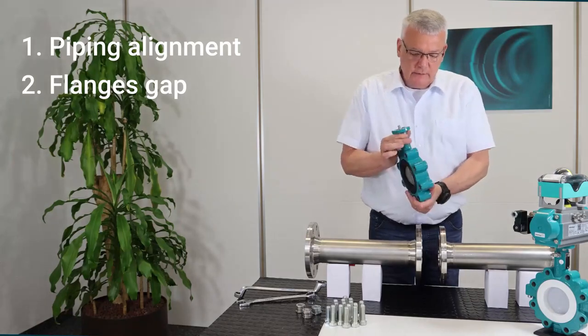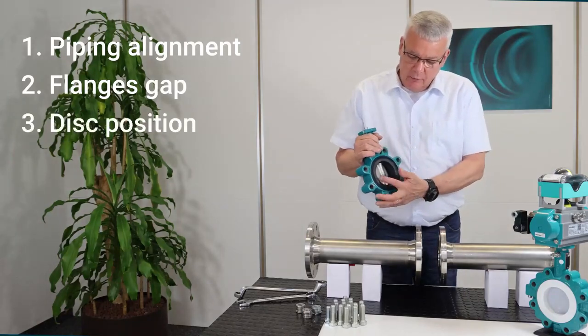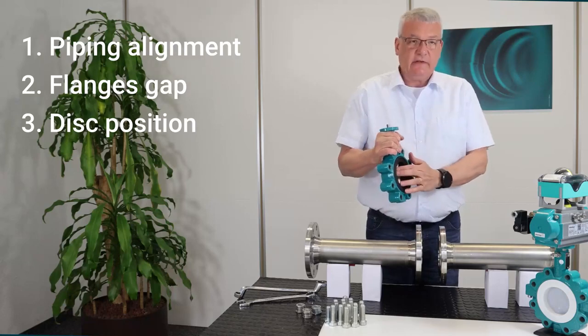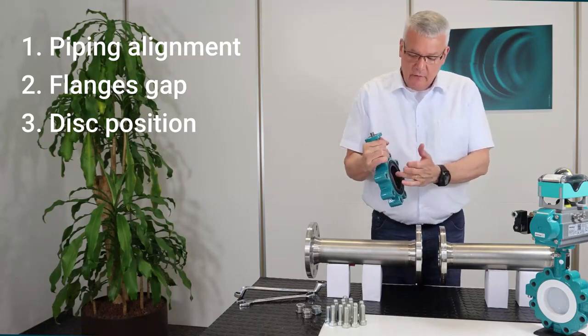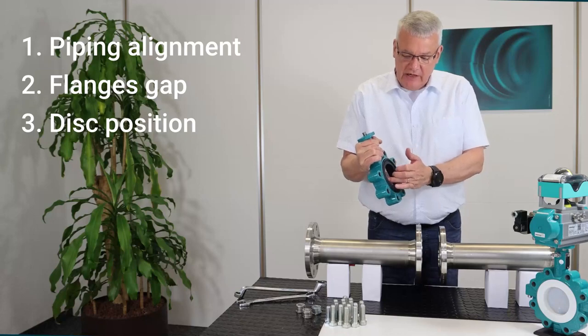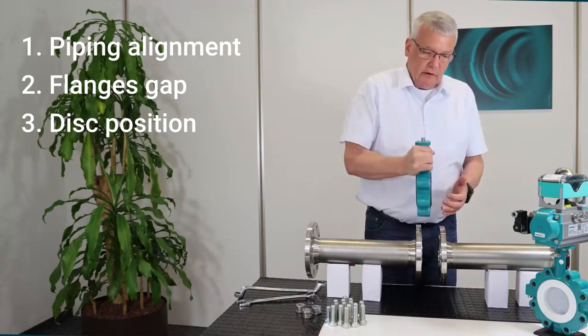You should make sure that the disc is in a slightly open position, but so that the edge of the disc is not appearing out of the valve body, otherwise you might risk damaging the edge of the disc when you install it between the flanges.